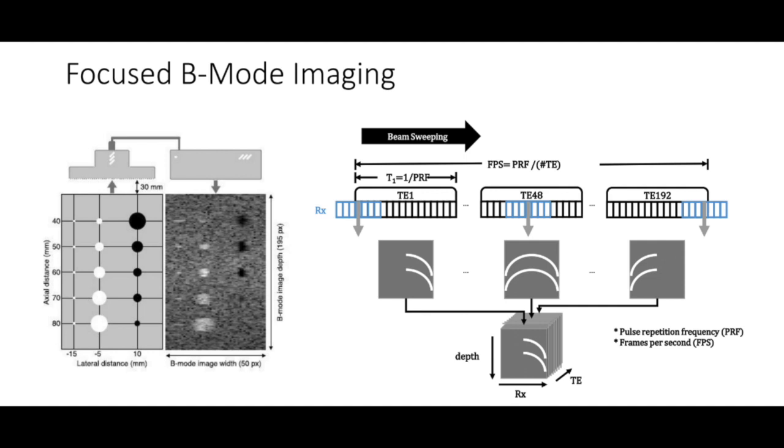Because of the continuous nature and time reversal property of sound waves, we can use multiple receivers instead of only one receiver to capture enough energy, so we can get a high quality image after image processing. Even though we have 192 channels in the transducer, we only use 64 channels to create one line in the image. The packets of channels used for creating the image keep shifting as the image is visualized line by line.